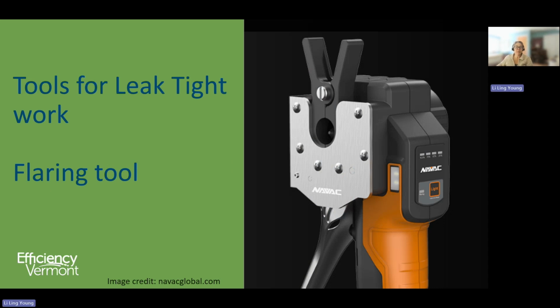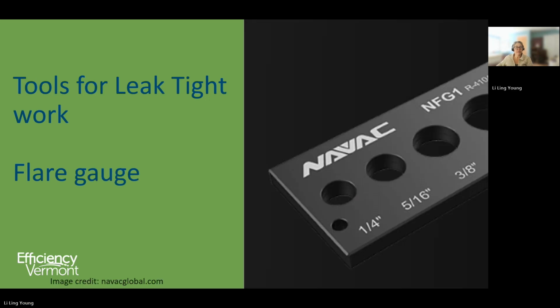The next step in making a perfect flare is forming the flare. This is a powered flaring tool that I'm showing. The clamp has a stop that ensures the tube depth is correct, and an eccentric or off-center cone rolls around the inside of the tube to stretch it out and make the correct flare angle. There are simpler tools that can do a good job making a flare. Know your tool. Always use a stop and a gauge to ensure your flare is the right size.